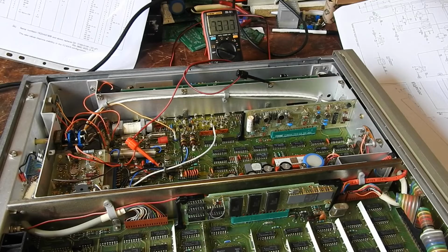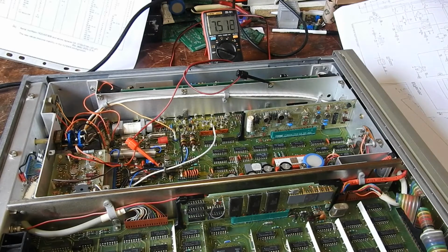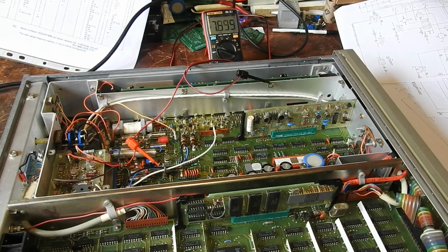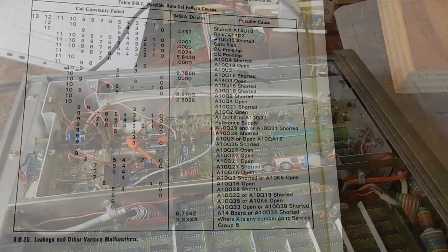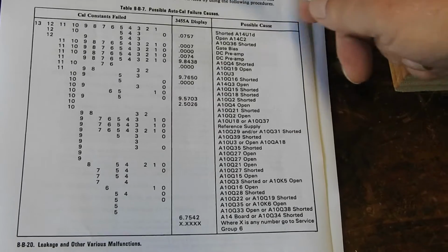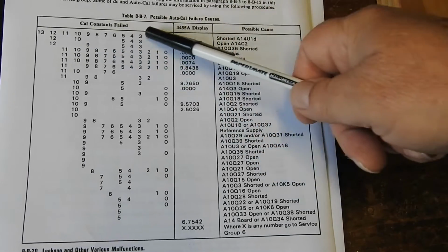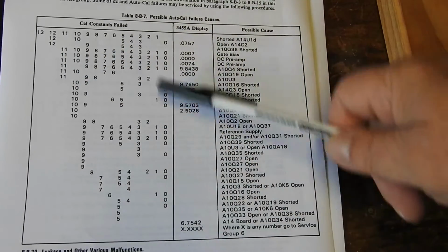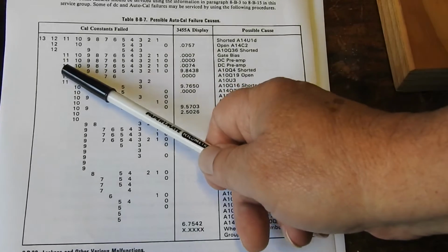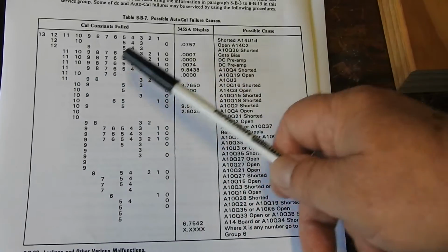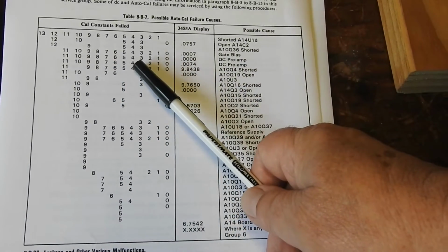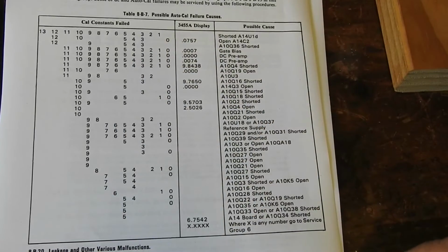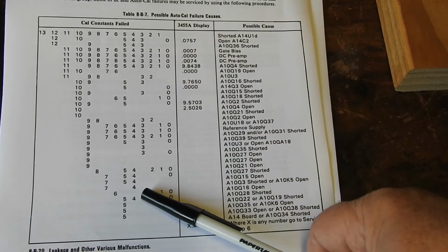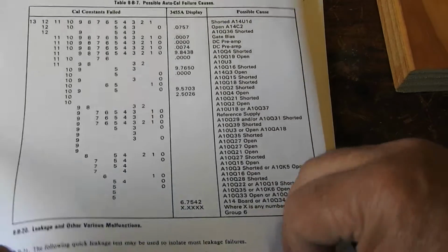I'm not 100% sure. I'm not at all sure what to make of that. I was hoping to get a shortcut by just looking to see what was dragging down the reference, but so we'll look at service group B. And looking at this table in service group B, cal constants failed, and there's no combination there that matches what I'm getting, which is 11 through to 0 failing, except 7 and 4. There's not that pattern there. There is 7 and 4 by themselves.